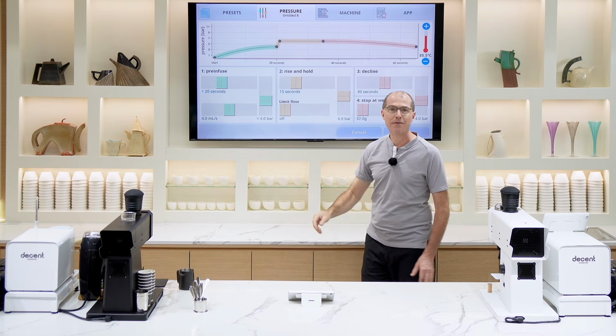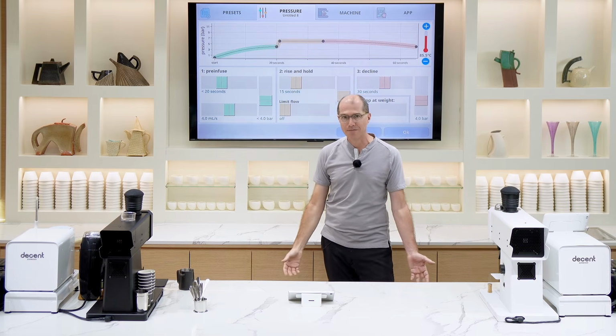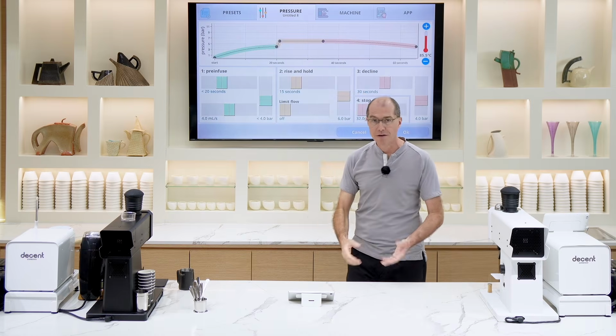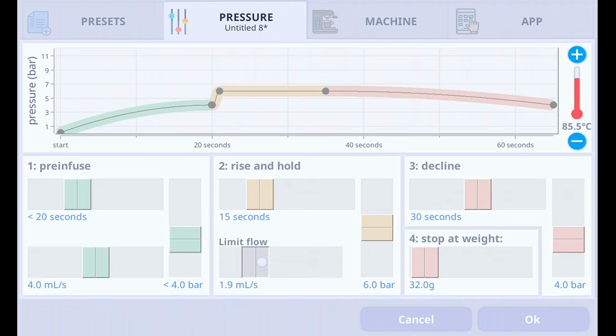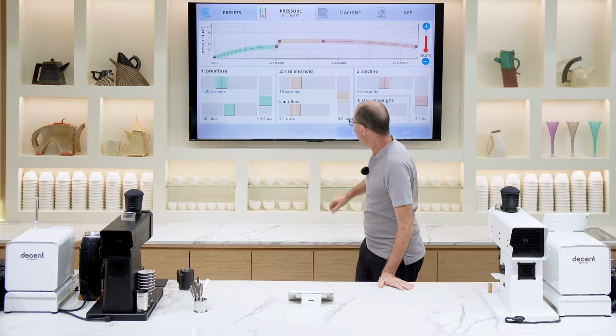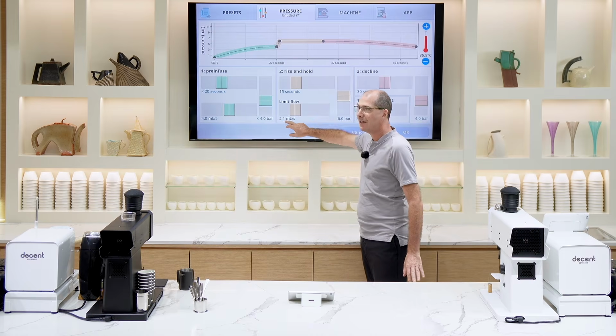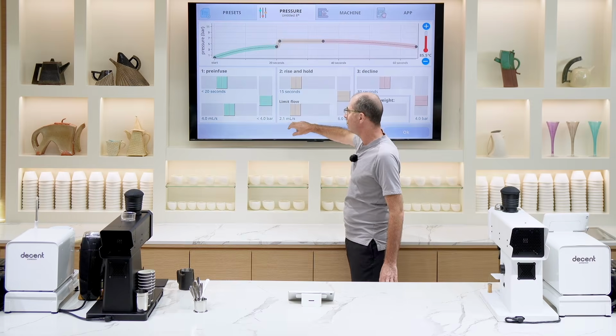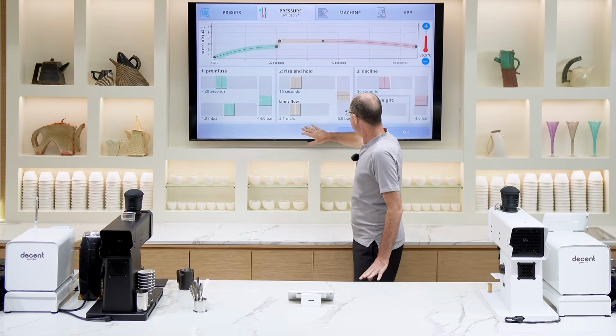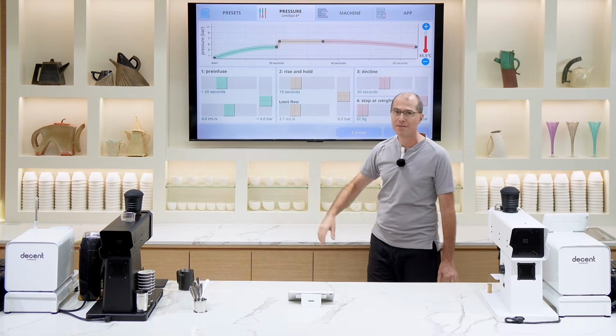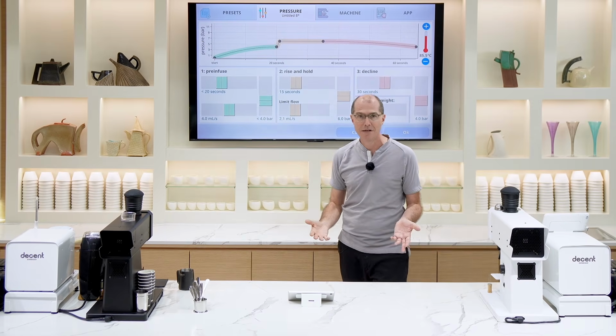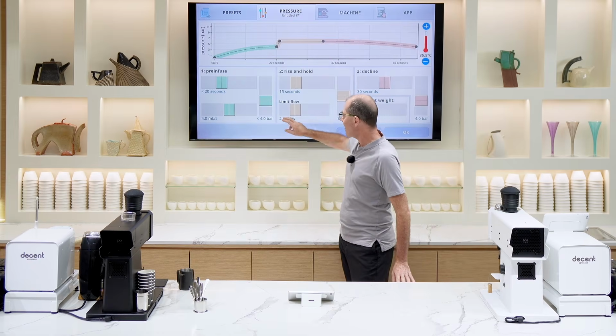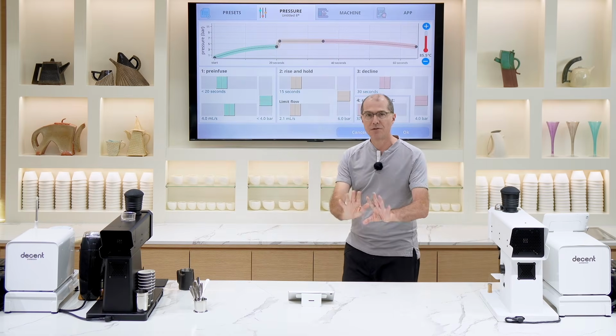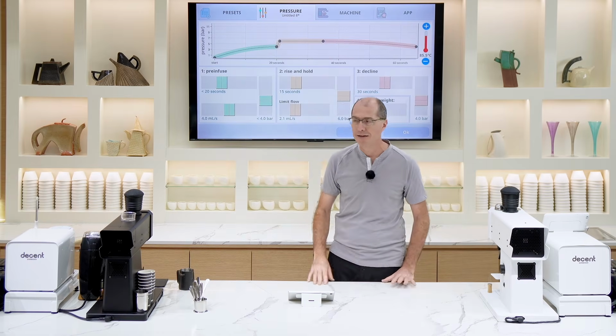What that is, if you've ground far too coarsely, for example, you might have a lot of water gushing through. If you want to limit that from happening, you can say limit flow. And here I've limited it to 2 mils per second, 2.1. What that means is as the pressure goes up to 6 bars, if the grind is too coarse and we go faster than 2 milliliters per second, then don't try and go to 6 bars, just do what you can, don't go over that.